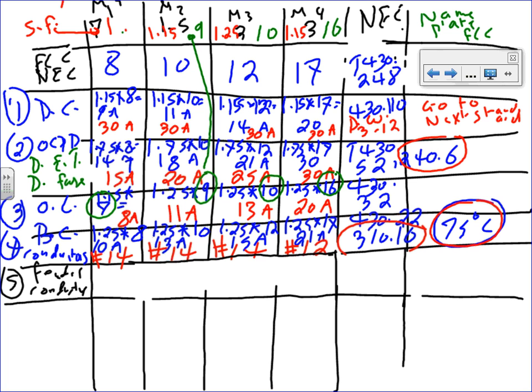Do you see what I mean? You only need 10 amps and number 14 can give you 20. So it's good. And that's the smallest that you can use. Maybe your question is, why can't I use 16 or 18? Because the smallest conductor in any code book that you can use for power, lighting, and equipment. Not for control though. Control you can use 16 and 18.